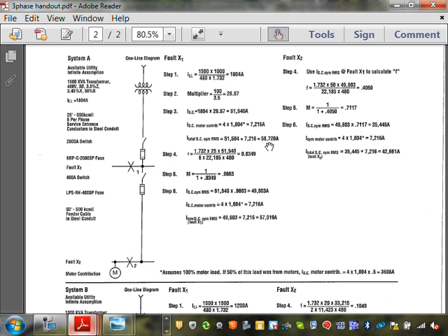25 is the feet. This is a short circuit. 22,185, this is the C factor. They call it the C factor for the cable. And there's a lot of tables, guys, that can get you this calculation. Now, when you go to step 2 here, you're going to take the value here and start doing calculation based on the impedance. We have one cable. Here's the C factor for this cable. Here's how far it goes. Available short circuit, the voltage. This will be your F factor.